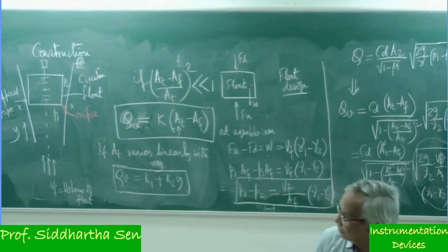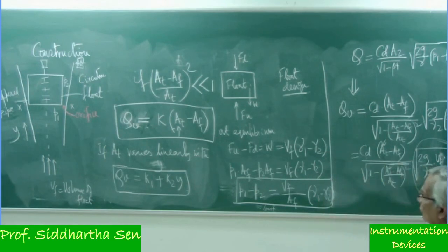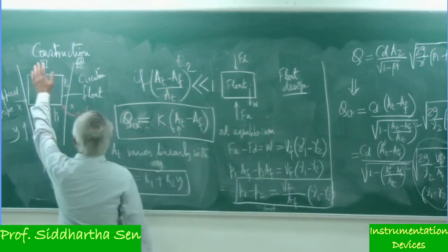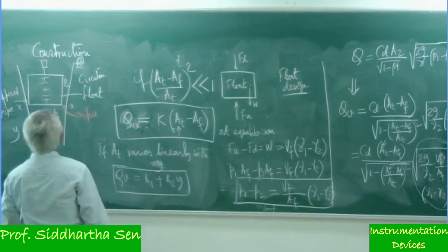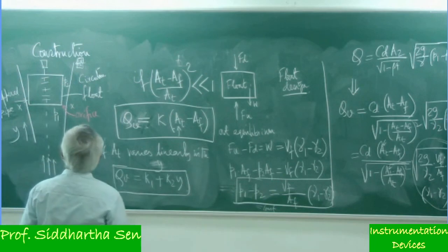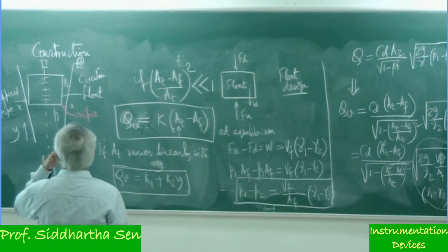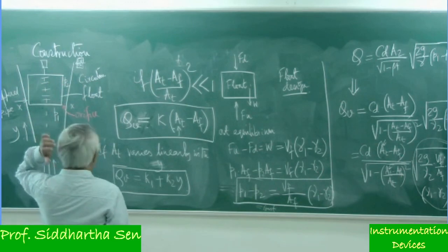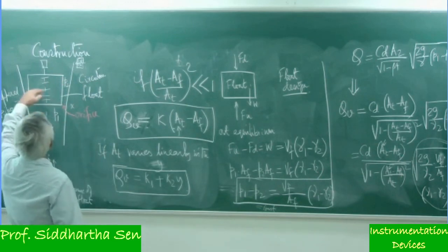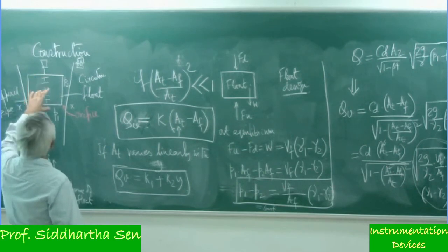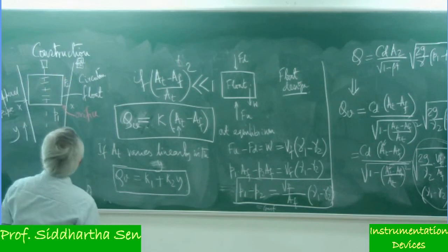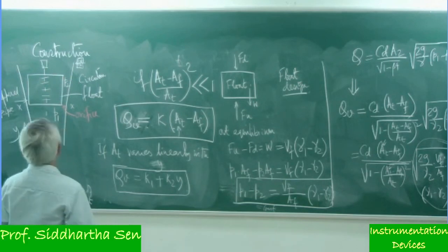So, any question? A few things to be remembered: it has to be always vertical. If it is inclined, then there will be an error in it. You cannot measure it correctly. And the float has a particular design, but you can see graduations on a glass tube, or you can generate some electrical signal using an LVDT core.